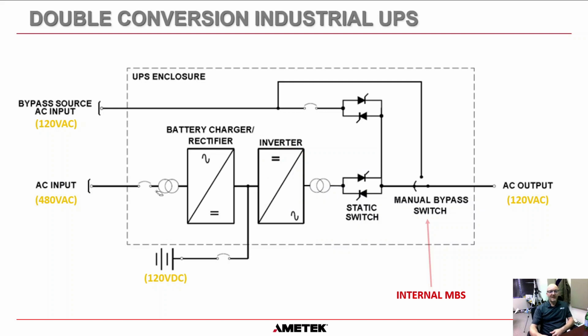And you can see on the left-hand side, we have our AC input voltages, 480 volts AC for North America into the battery rectifier. And if it's a single phase output UPS, then you're going to have a single phase bypass source as well. And then in this system here, we have a battery that is 120 volts, which is once again pretty much standard for North America for a 60 cell lead acid battery.